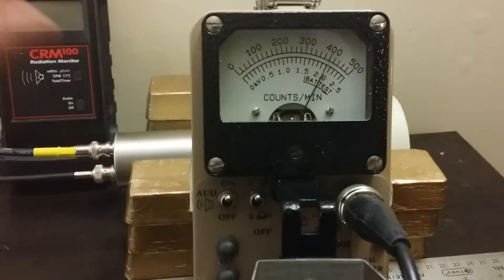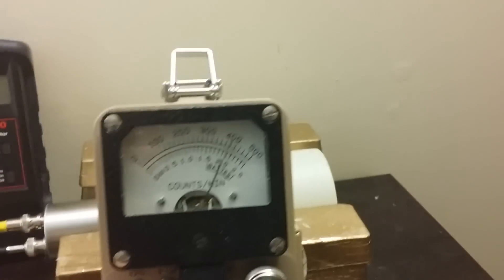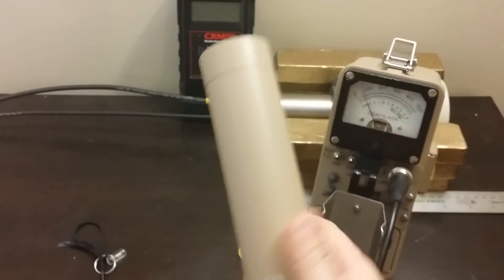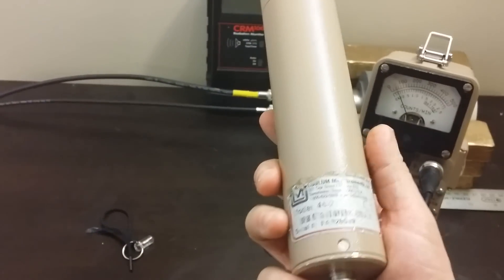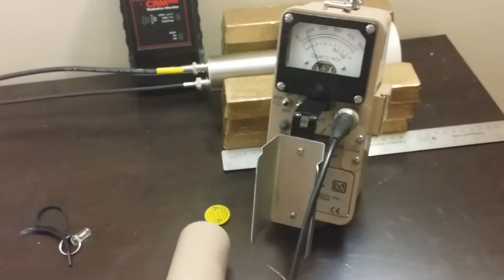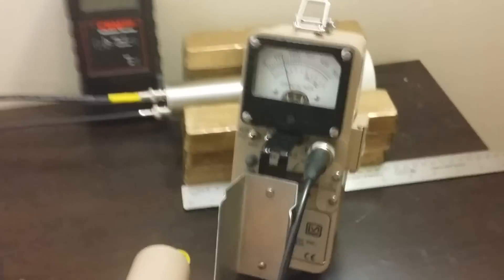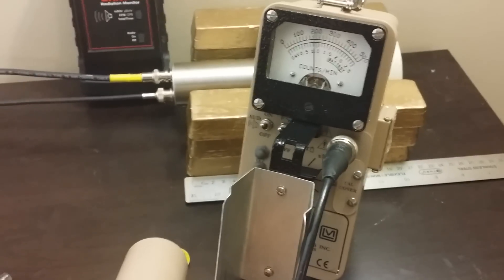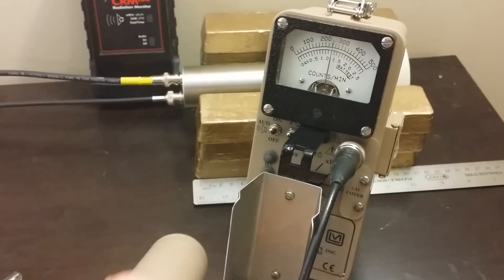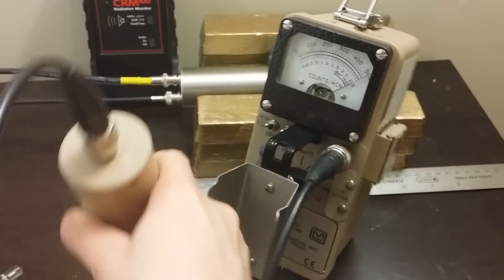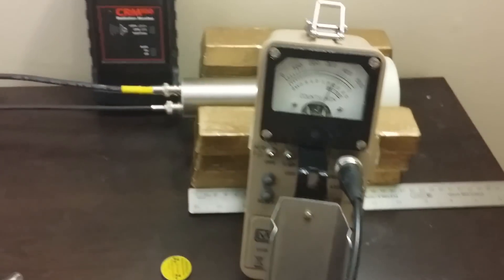Cut the sound on. We'll adjust it to times 100. Currently, I have a 1-inch sodium iodide detector connected. It's a Model 44-2. As you can see, we go near the Cs-137 sample and the reading goes up. And we pull away, it goes down.